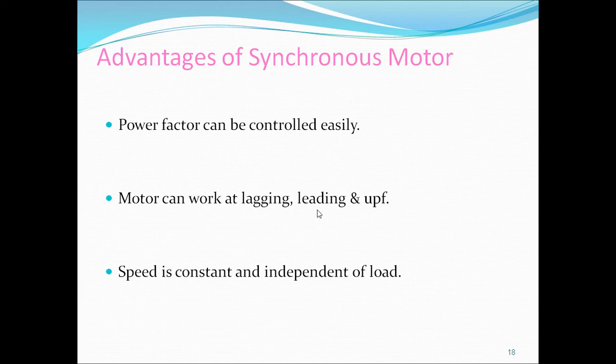Speed is constant and independent of the load. That means however much load you apply, it will still rotate at synchronous speed, that is the rated speed. If you put some more load, it will still run at synchronous speed. If you keep increasing the load like that, then at a particular instant the motor is not going to bear any more load. At that time it comes out of synchronism, and the motor stops.